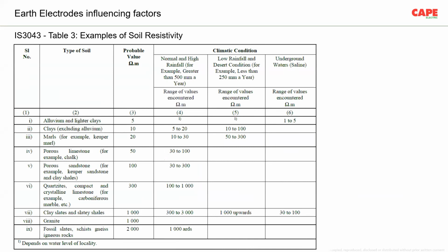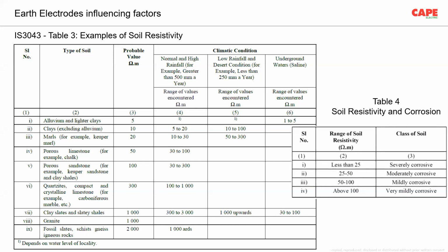Now, a technique used to reduce this earth electrode resistance is to have something in the soil surrounding the earth electrode, in the area surrounding it, which may influence and reduce the resistance of the earth electrode. First, what we should understand is what soil resistivity is. Soil resistivity depends on the type of soil. I'm sure most electrical engineers know this particular table. The probable resistivity value in ohm meter depends on the kind of soil. You can see the values 5 ohm meter, 20 ohm meter, 50 ohm meter, 300 ohm meter, 2000 ohm meter, like that. What you should also keep in mind is corrosion.